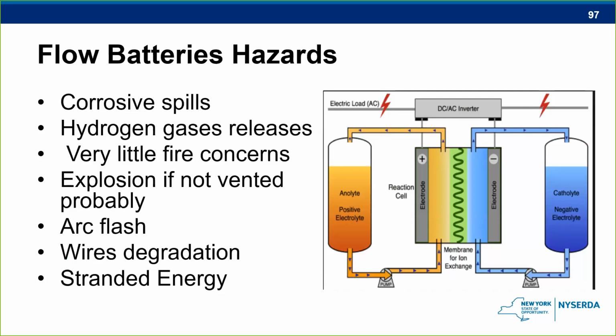There is one up in Jacobi Hospital in the Bronx, and they have a lot of different things to make sure that the corrosive does not spill out. So there's secondary containment and also tertiary containment in those situations. If they do overcharge, though, they do release hydrogen. The nice part about the one in the Bronx, any of that hydrogen was supposed to be pushed right outside the container itself, so it would never build up in the container. But they do still have hydrogen monitors inside the container or the enclosure itself to make sure that if this stuff does build up in there, it will send something to the fire department.